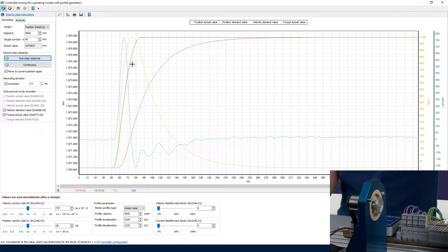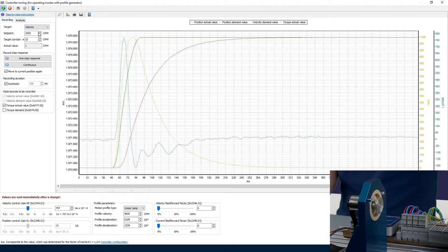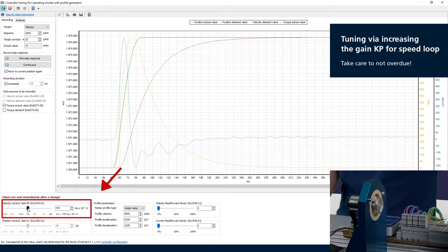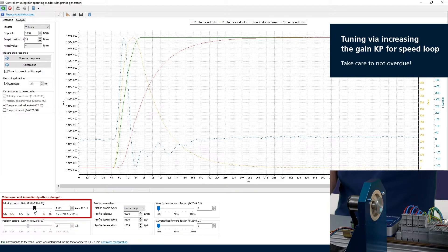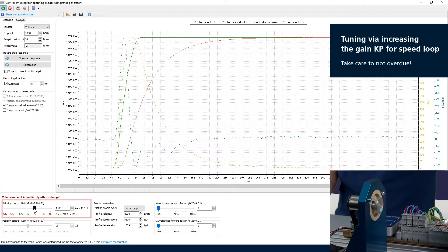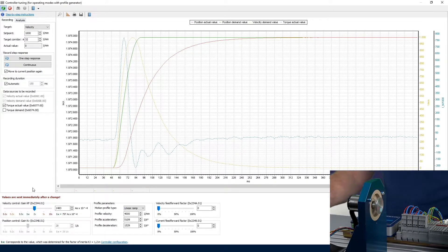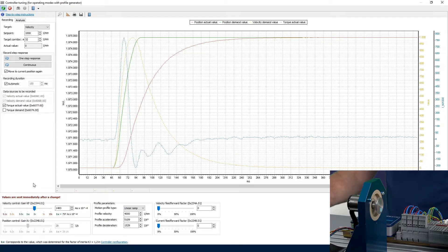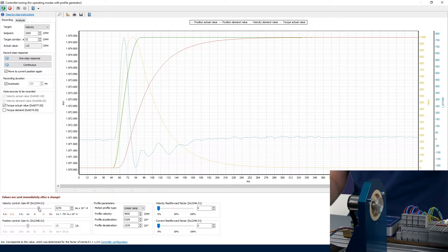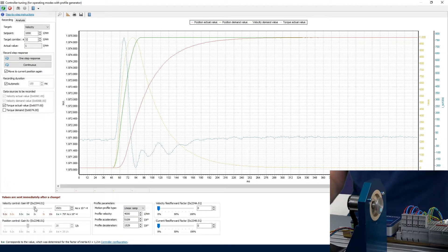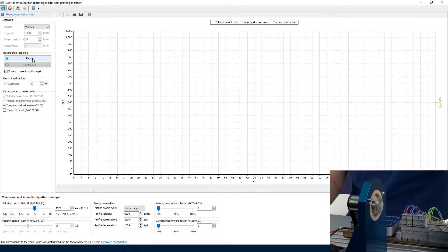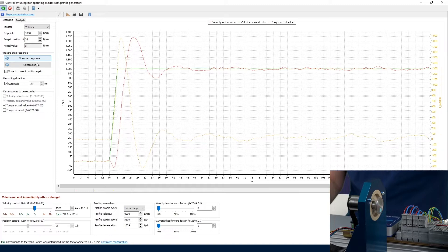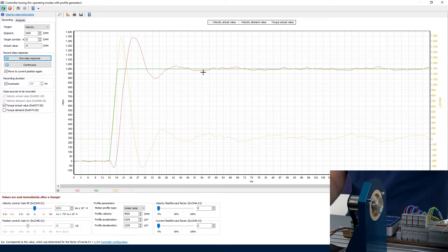Now we could tune starting with the speed loop, and tuning is increasing the gain down here. Typically a value of two should be possible with such a low inertia, but you might hear it in the audio of this video, it's getting a little noisy. So if I increase it more here, then it's definitely unstable, so don't do this. Don't overdo the increase of the gain. And then of course when I do this step again, that's what our application note explains: one overshoot, one undershoot, and then we are in the corridor.